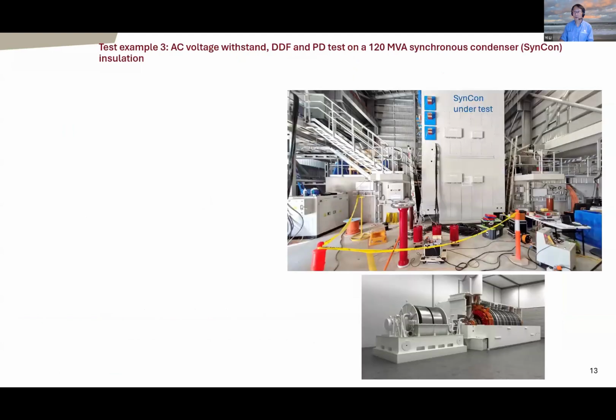This is another very good example. Say this is a so-called synchronous condenser. It's 120 MVA. Synchronous condensers now, like phase shifting transformers, are getting more and more used in the power network. It's because of renewable energy. Basically, it provides additional inertia to the network. Its design is very much like a generator. So this is what it would look like inside.